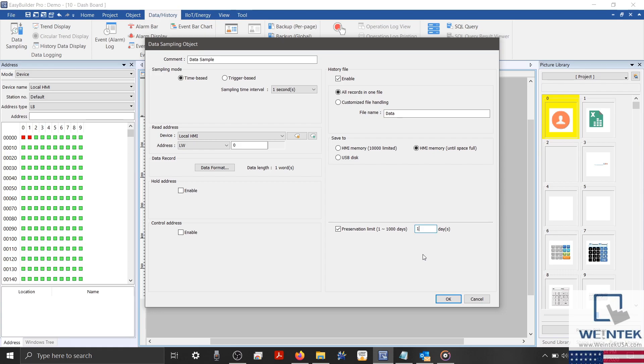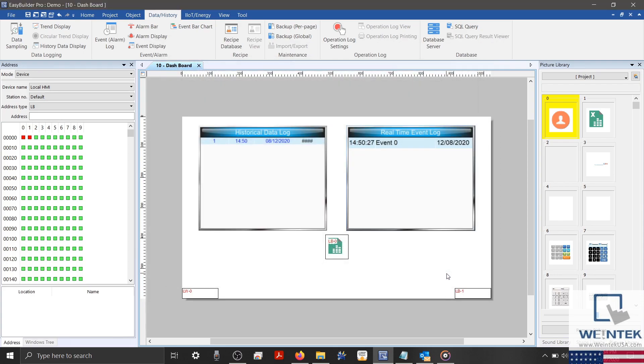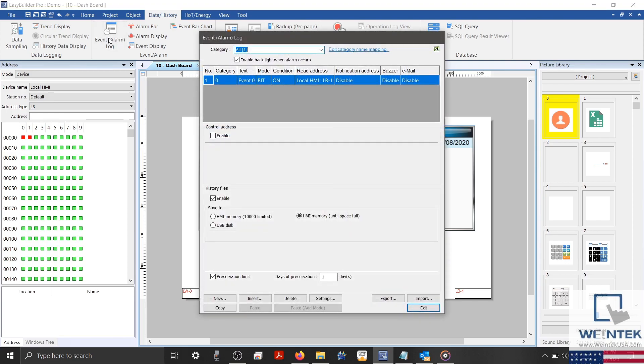With the overview of our data sampling object complete, let's close our menu and review the settings of our event log. The event log can be found within the Data/History tab, next to our Data Logging button. Within our event log, you'll notice that, like our data log, I have enabled history files, the storage location is configured to our HMI's internal memory, and our preservation limit is set to one day. Although these settings will likely vary depending on your application, we must ensure that history files is enabled.